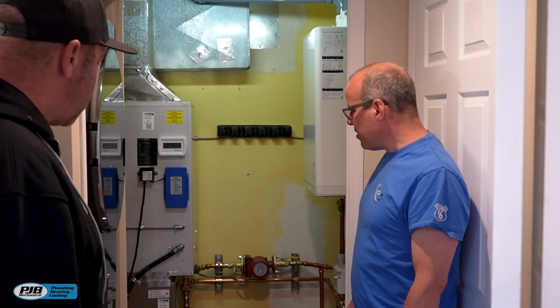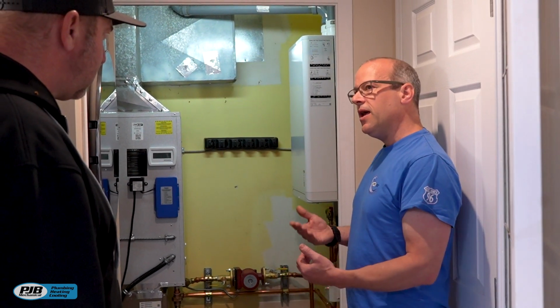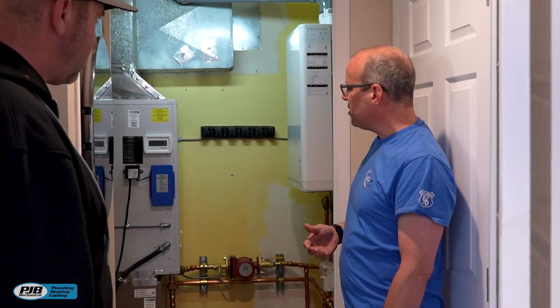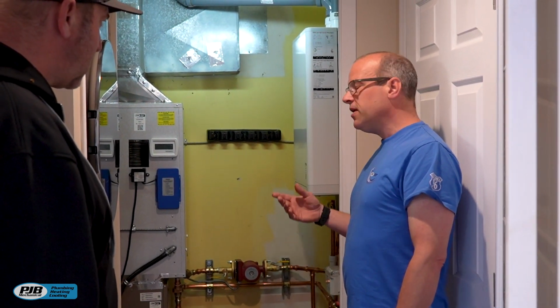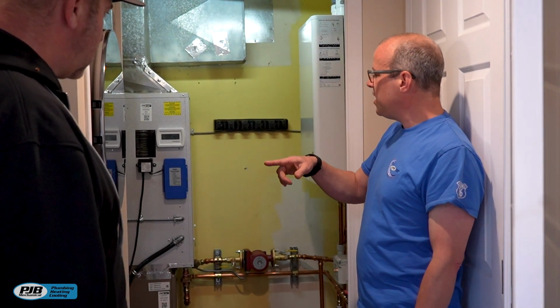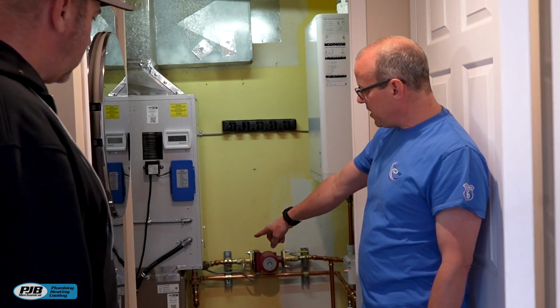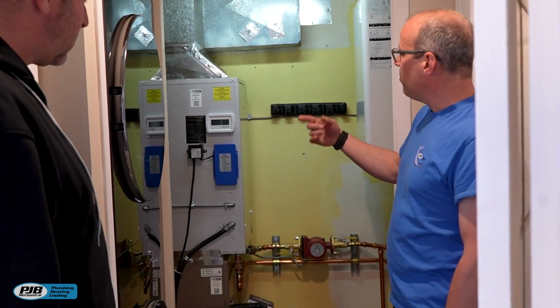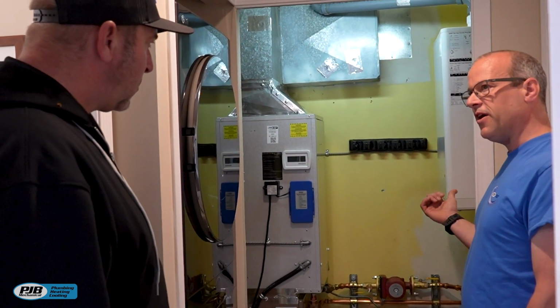So some of them work, but all heat pumps will lose efficiency the colder it gets outside. Because we have it set up on what's called an economic balance point, the system knows how cold it is outside, and it will actually disable the heat pump portion when it's more efficient to run the gas-fired heat.